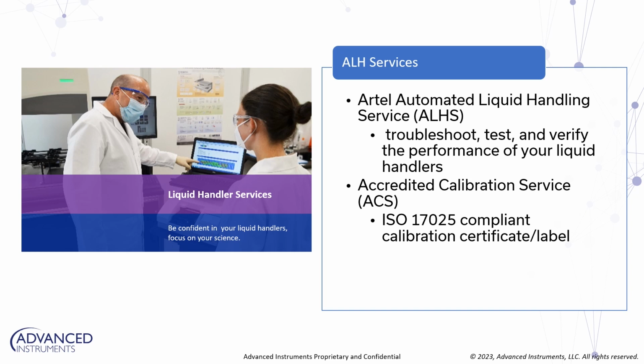The accredited service, the ACS, is the first on-site ISO 17025 accredited calibration service for automated liquid handlers. After that service is delivered, the specialist will produce test reports for each test, which include well-by-well and tip-by-tip measured volumes, summary tables that can be opened in Excel, and of course, calibration certificates from our ISO 17025 accredited team.